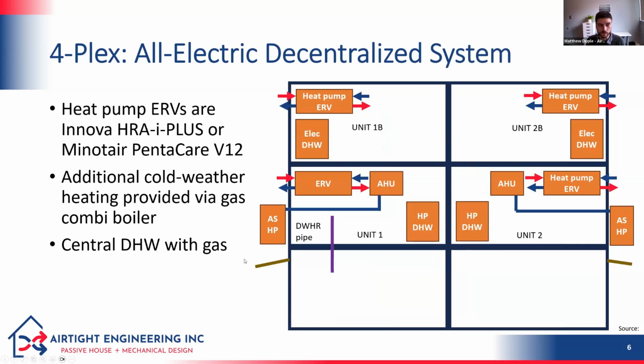A completely decentralized option would use heat pump ERVs in the two top suites, since they have small enough loads, with electric domestic hot water tanks for their small hot water loads. For the main floor units, I propose ERVs feeding into an air handler with an air source heat pump and a separate heat pump hot water heater - similar to what we'd design for a larger house. That's my proposal for a completely decentralized system.